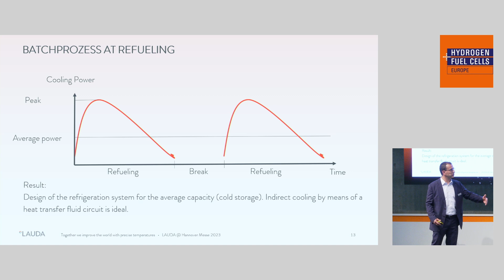With the direct cooling system, the evaporator is directly in the cooling plant, more or less, and you need the evaporator directly at the dispenser. With our indirect cooling system, we use a heat transfer fluid: the evaporator is on one side and only a heat exchanger is at the dispenser, connected via the pump and heat transfer fluid. Our solution also includes a cooling storage in the system.